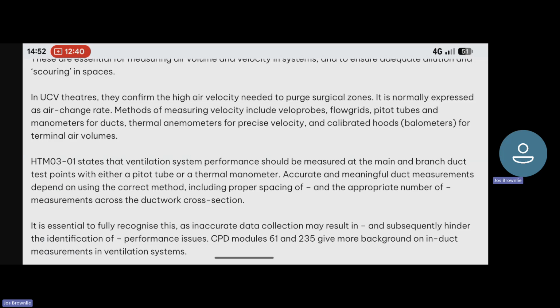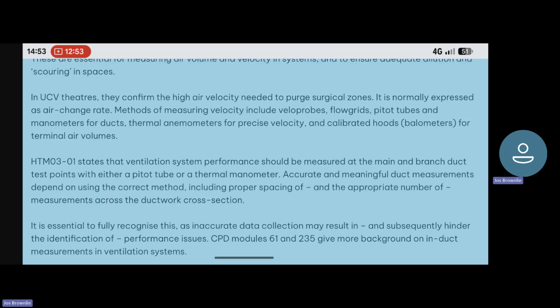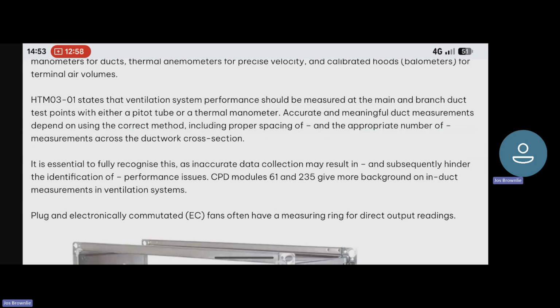Methods of measuring velocity include veloprobes, flow grids, pitot tubes, and manometers for ducts, thermal anemometers for precise velocity, and calibrated hoods or bolometers for terminal air volumes. HTM 03-01 states that ventilation system performance should be measured at the main and branch duct test points with either a pitot tube or a thermal manometer.